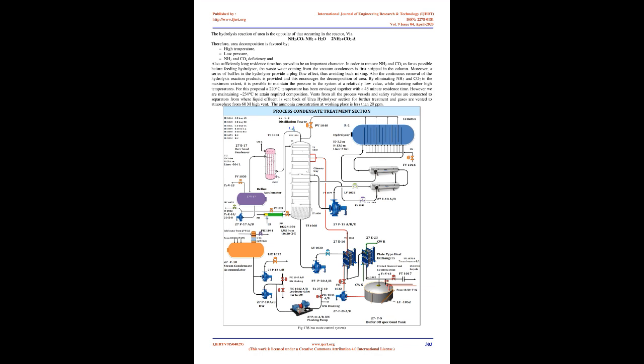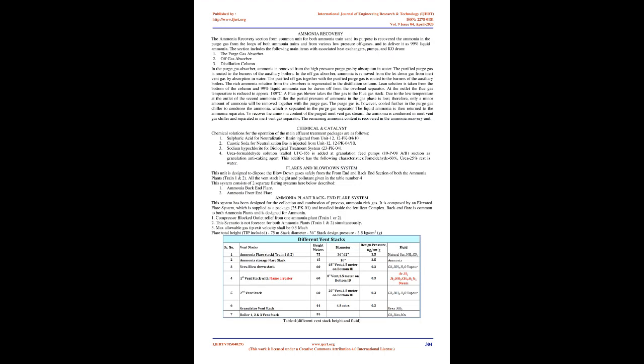Flares and blowdown system. This unit is designed to dispose of the blowdown gases safely from the front end and back end sections of both the ammonia plants, train 1 and 2. All the vent stack heights and pollutants are given in table number 4. This system consists of 2 separate flaring systems described below. 1. Ammonia back-end flare. 2. Ammonia front-end flare.